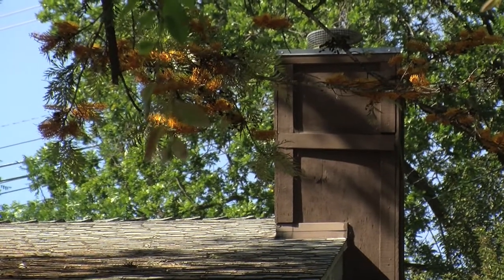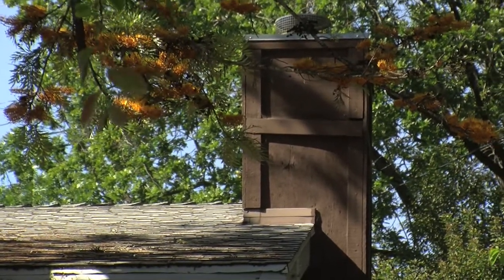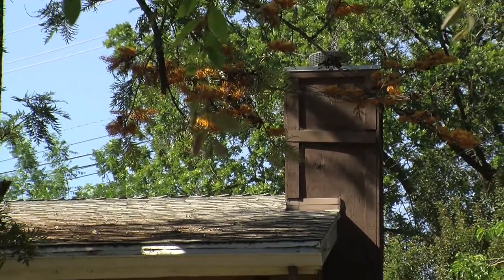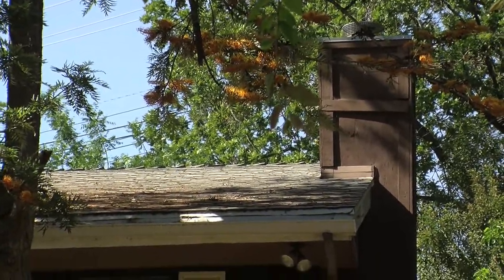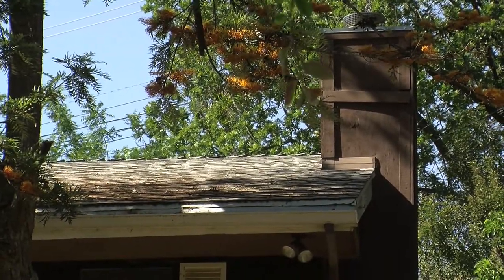So another location on a roof that can be vulnerable to debris accumulation and ember ignition would be a chimney chase that has a combustible wood siding or a combustible siding. It can be wood or vinyl, any kind of combustible siding. If debris accumulates against that siding on top of the Class A roof, it is the siding that would be the vulnerable part of the assembly, not the Class A roof itself.